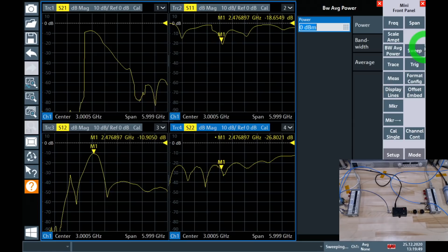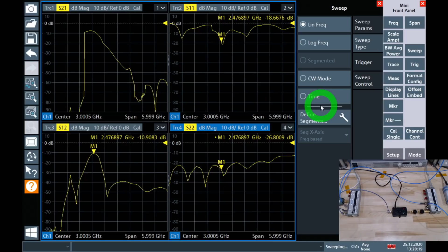Now there are a few different types of sweeps you can do on this instrument. If I go under sweep, I can do sweep types of linear frequency, log frequency, CW mode, and time. One of the sweeps that's missing, that should be very easy to implement, or at least I couldn't find it, is a sweep of power. In this case, a sweep of power would have been very useful. We can put it into CW mode, fix the frequency, let's say at 2.4 gigahertz, and sweep only the power, allowing us to see exactly where the transition point is between the two modes of operation. I would like to see that added to the firmware. At least I couldn't find it, but it's pretty straightforward to do if they wanted to.